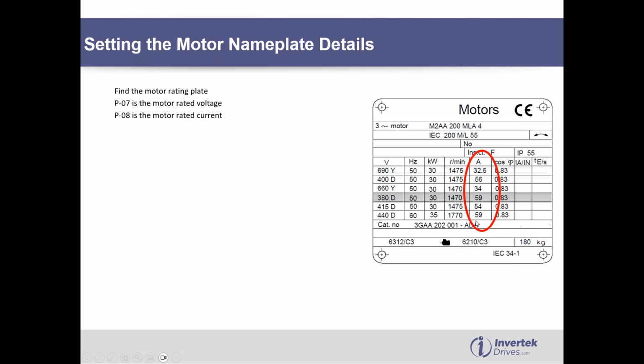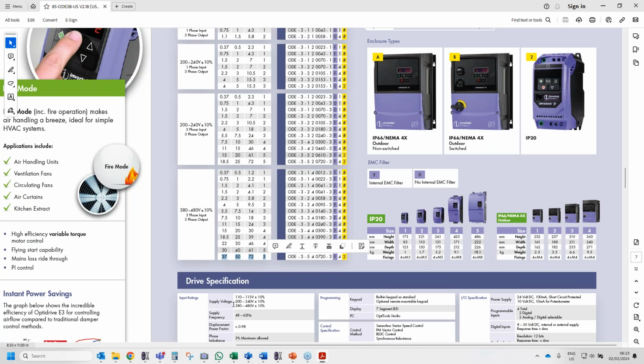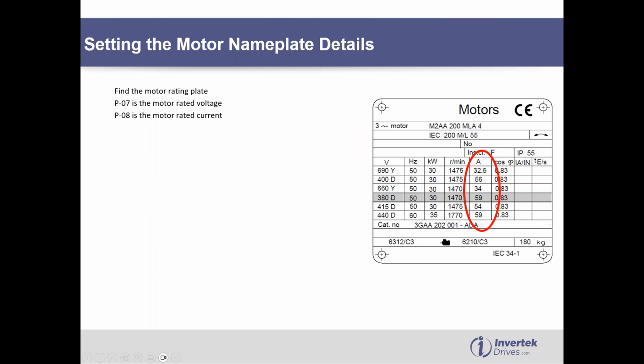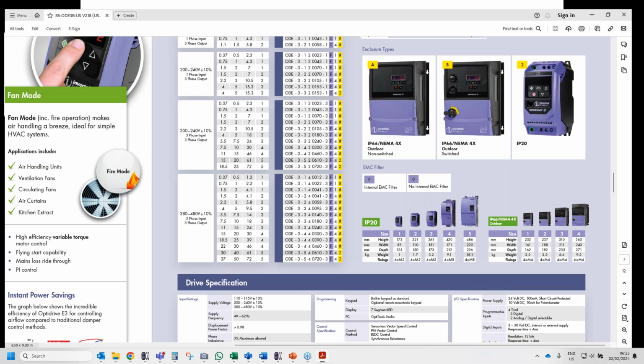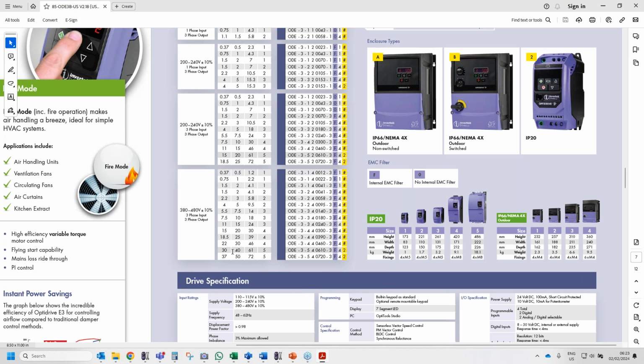So here, in this situation, if your customer says, oh, I've got a 35 kilowatt motor, a lot of people would just go and choose a 37 kilowatt drive. I ask the customer, what's your motor current? And he says 59 amps. So here then, I've actually gone down one size, because this drive, even though it says 30 kilowatt, can give 61 amps. So that means that I could be cheaper than the competitor. So this is why it's so important to use the motor rated current, not the kilowatts or the horsepower. Is that clear?